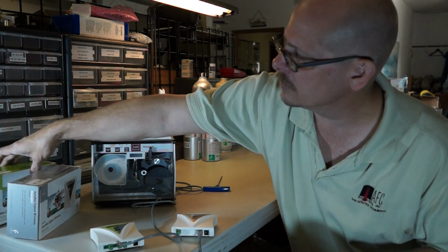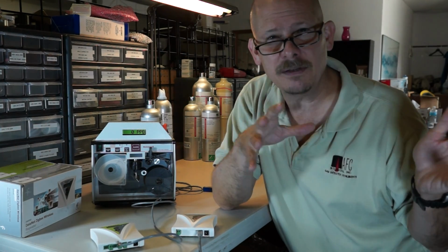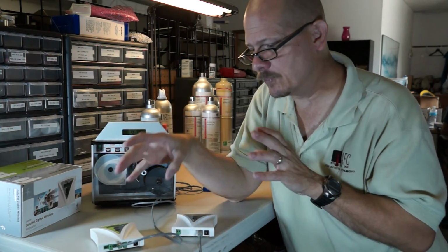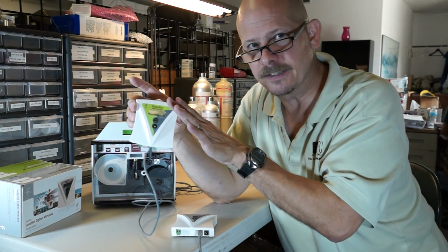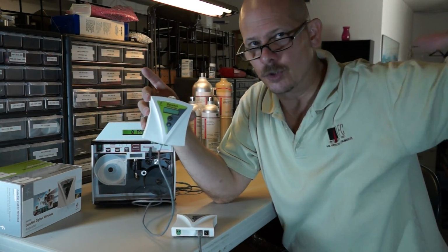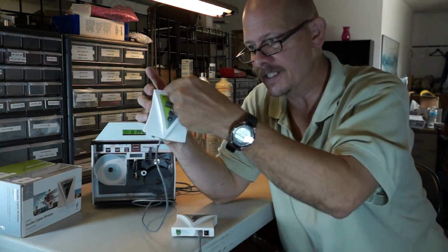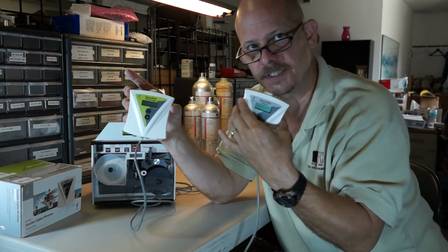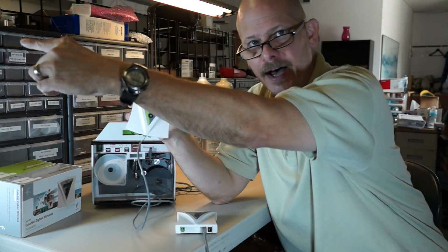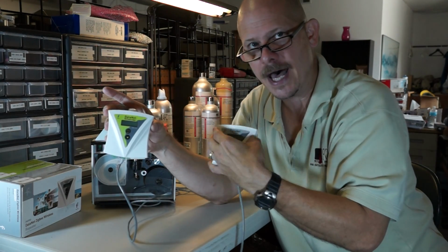What a Zigbee wireless system basically is, it's a mesh network. Mesh networks, Zigbee networks, all work on the principle that each one of these DataNet devices, if you had, let's say, 100 of them throughout the plant, or 20 of them, or 10 of them, not only do they just send and transmit back to the receiver, but they also will find the path of least resistance if that direct path is blocked.